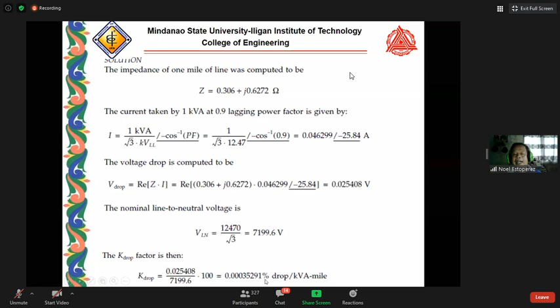So the K factor will be 0.025408 over 7199.6. This is a way of determining a K factor. If we multiply this by the load on that part of the system and the length of the line, we can get its voltage drop directly. So for a certain segment in the distribution network, we will apply this in this case.